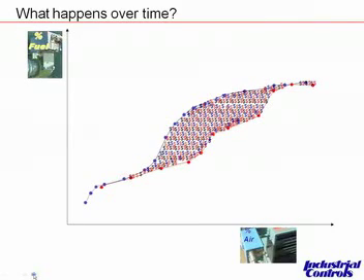The person's there, we're watching it, we set it up, we leave it where it needs to be, but understanding that the linkage through time is going to wear, the person will probably leave some excess air in the combustion process to assure that we don't make unduly great amounts of carbon monoxide. So what we end up with is the blue curve.